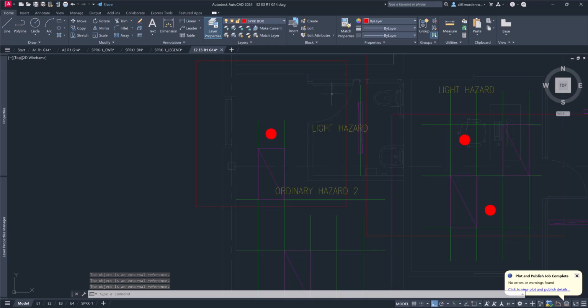Something also students kind of mess up sometimes is that my box looks like it can enter this room. However, it cannot. Okay, so whenever you have a sprinkler, it can only go as far as the wall, right? So that's as far as it can go. So the next one that we can put in here, say, is we need to put 8 feet, right? So about 96-inch spacing.